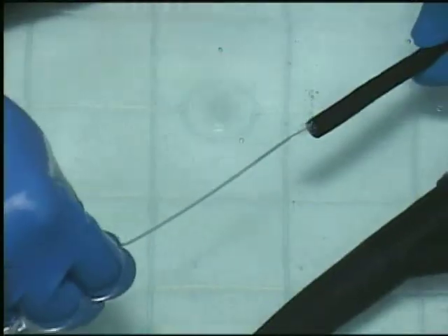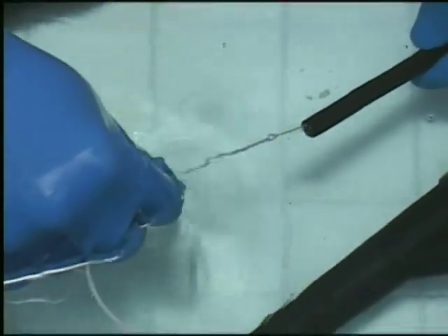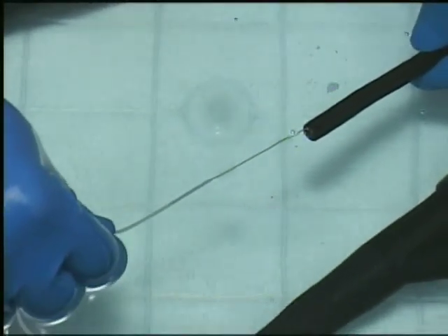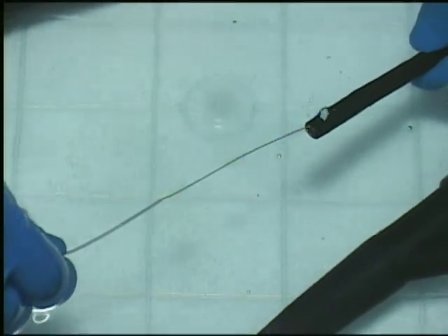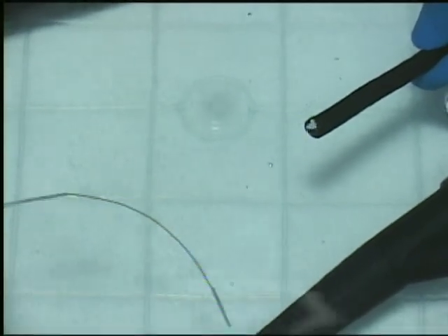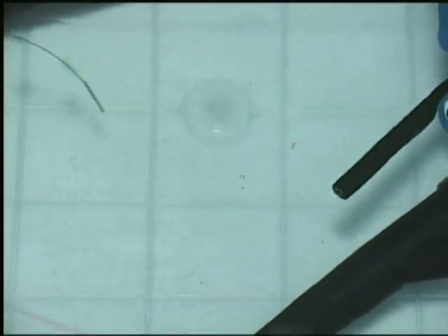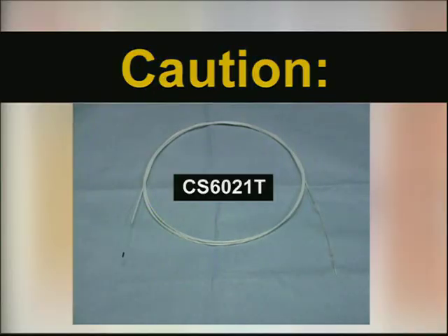Grasp the back end of the brush shaft and gently pull the brush from the scope distal tip. Do not use excessive force. Repeat until bristles are visibly clean. Caution: the CS6021T brush is for one-time use. Never reuse the brush on more than one endoscope.